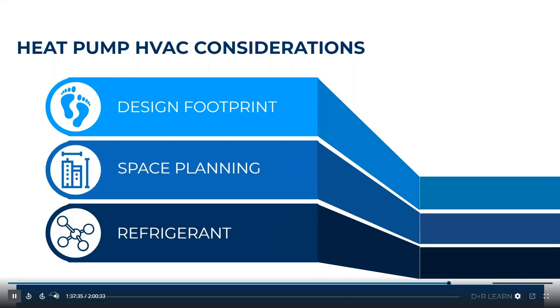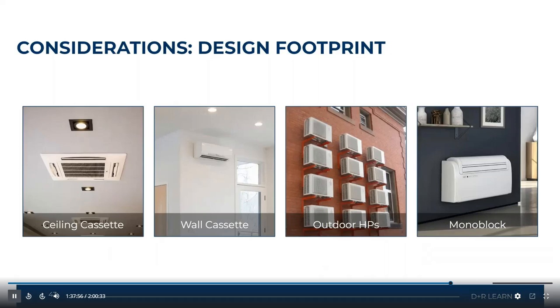Now, I do want you to keep in mind when referring to refrigerant, there's an important part that we're going to talk about, which has to do with safety and code requirements. And this deals directly with ASHRAE codes 15 and 34. We're going to talk a little bit closely to that here as well. So not code considerations, but considerations on installation when talking directly to design footprint.